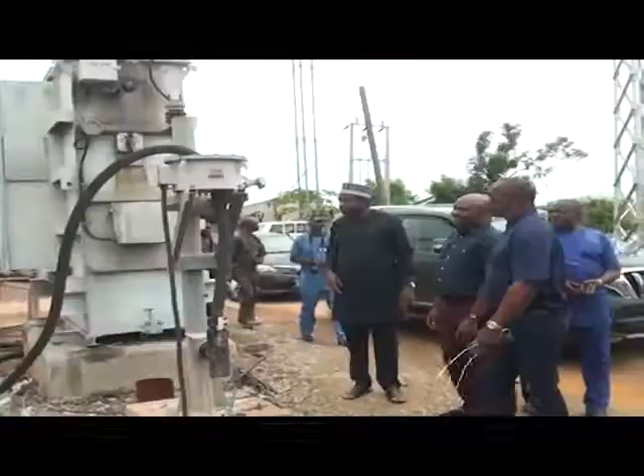You can't say a big town like Abeokuta, we are serving them on 2 by 30 MVA. It's heavily constrained, or 3 by 30 MVA. That means you are talking about 90 MVA. And if you factor the fact that these transformers are old transformers, that are derated, there are certain capacity they can carry. It means that they may not be carrying more than 60 or 70% of their capacity. That tells you that we have a serious load constraint in this place.